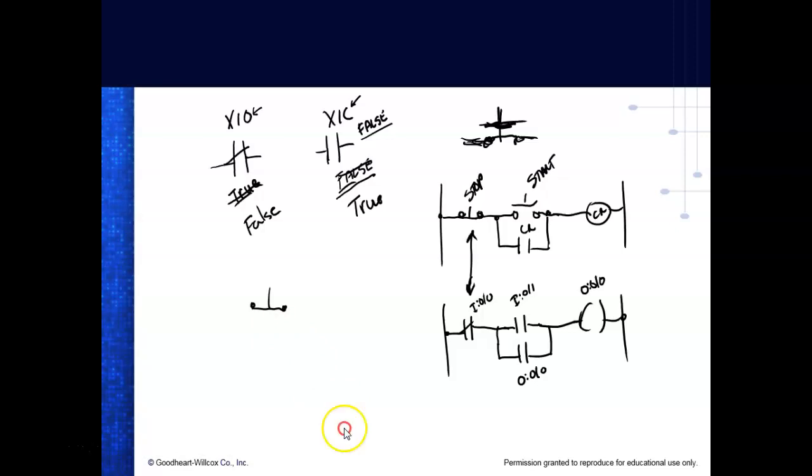breaks. So what would happen is this right here now would be what? This is an examine if open. Well, by George, it's closed, so right there would be false. Right? You understand? Okay, so that means I can come over and hit this button right here all day long and nothing's going to happen. So the way this would work is some person would have to hold the stop button down all the time and press the start button. Because I'm using an examine if open.